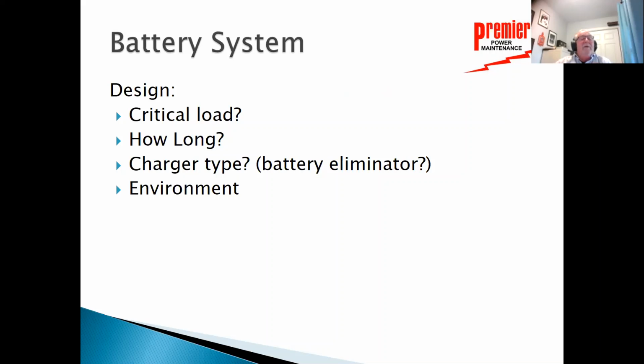So when we talk about design of the battery system, that has changed so much. What are our critical loads now? What critical loads do we have to have? What do we have to carry on? Again, with the new microprocessor-based relays, they're energy efficient, but that's a load that we never had on before. We just had light bulbs when I was a relay engineer years ago.